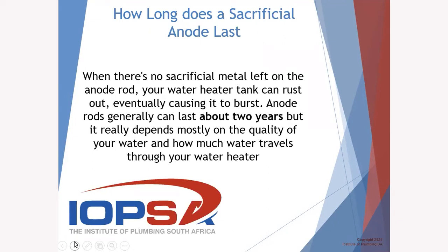If, for example, there are 4 people in a house and you just shower once a day, but if you come from a sporting family and each person showers 2-3 times a day, that water heater is going through many heating cycles, which will make your water heater more prone to corrosion than maybe the people next door. So remember, it's all about the amount of times that your water heater heats up. Because the more you heat up water, the more corrosive it is, the more it eats.